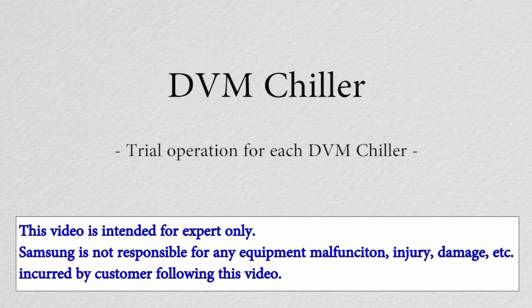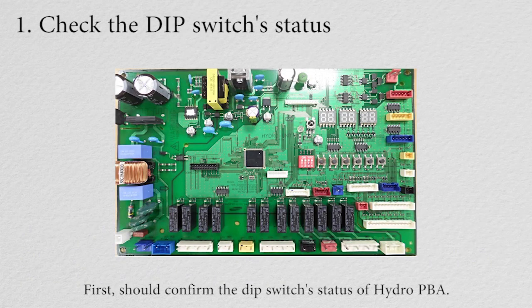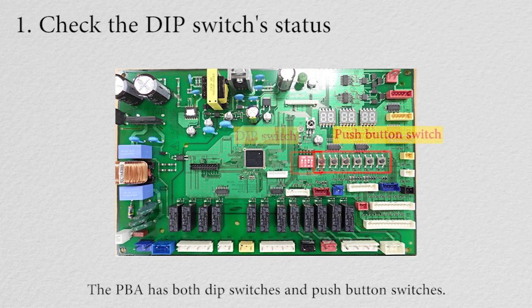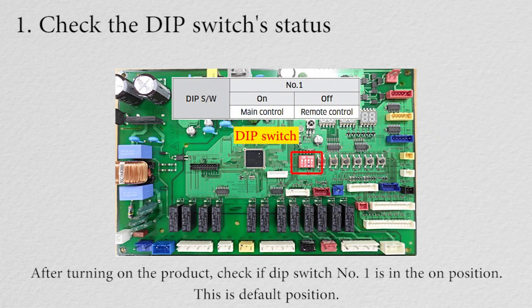This video explains the trial operation for each DVM chiller. First, you should confirm the dip switch status of the Hydro PBA. This is the printed board assembly located in the Hydro controller control box. The PBA has both dip switches and push button switches. After turning on the product, check if dip switch number 1 is in the on position.